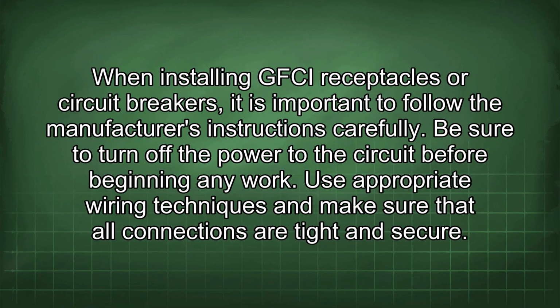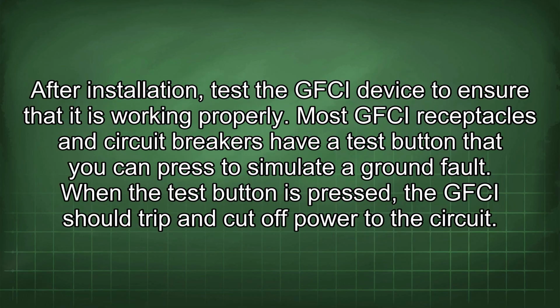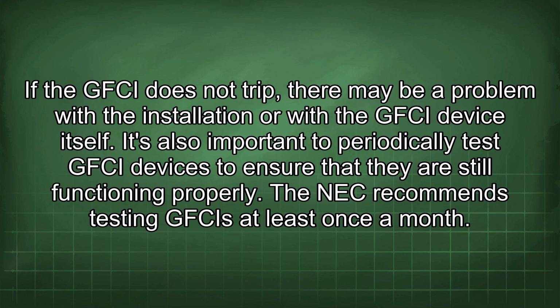When installing GFCI receptacles or circuit breakers, it is important to follow the manufacturer's instructions carefully. Be sure to turn off the power to the circuit before beginning any work. Use appropriate wiring techniques and make sure that all connections are tight and secure. After installation, test the GFCI device to ensure that it is working properly. Most GFCI receptacles and circuit breakers have a test button that you can press to simulate a ground fault. When the test button is pressed, the GFCI should trip and cut off power to the circuit. If the GFCI does not trip, there may be a problem with the installation or with the GFCI device itself.